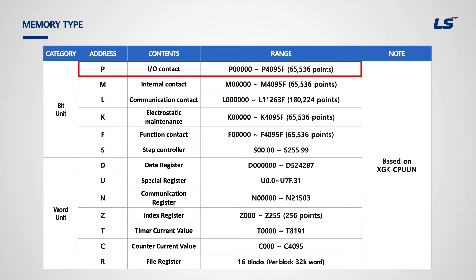For example, if there are input-output modules that use memory from P0 through P12F, then the rest of the memory from P130 to P4095F are not used, which can be used as internal memory. When users use the left-over P memory as internal memory, they might get confused whether the P memory is allocated to input-output modules.